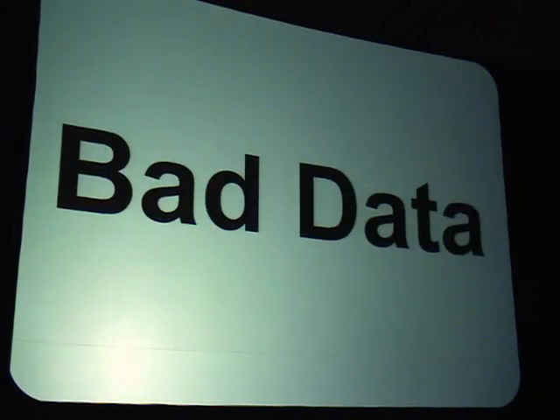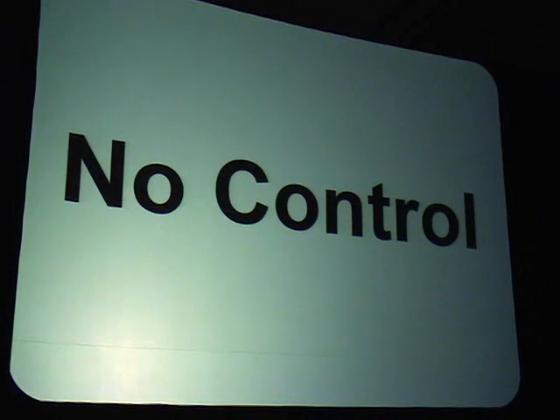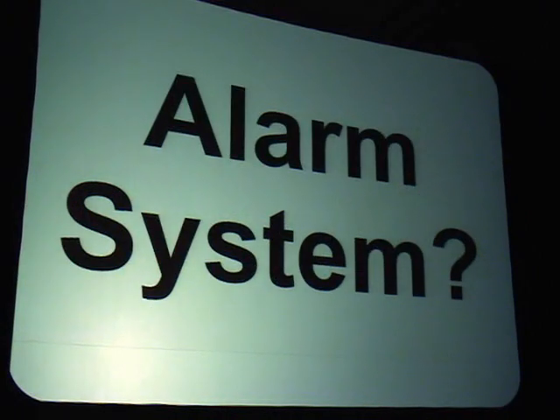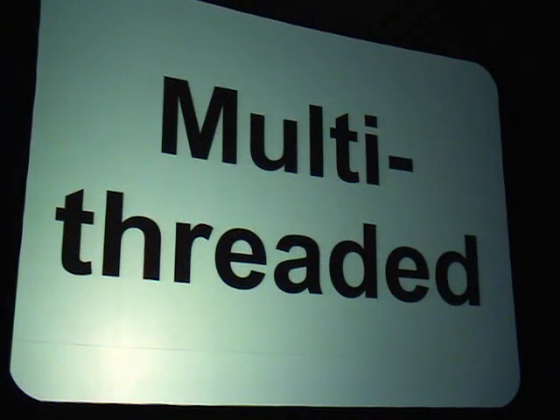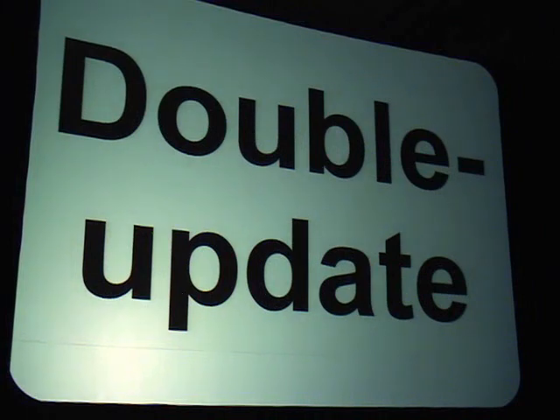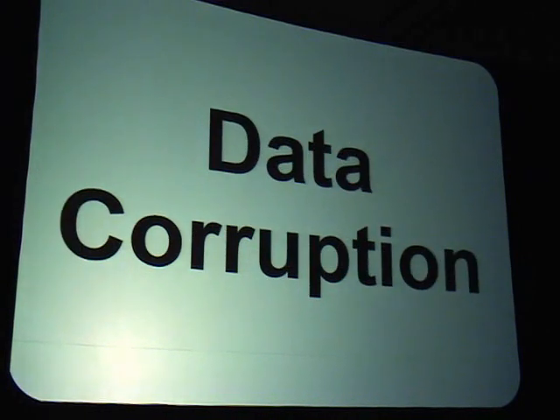But why did this occur? What was the root cause of it? Well, we know what the problem was with MISO. It didn't handle bad data very well. It wasn't very robust. But they didn't have control over the bad data either. But what happened with that alarm system? Well, the alarm system was a multi-threaded application, and it contained a race condition. Specifically, there was a double update problem. You could have 2 threads updating the same piece of data at the same time, and that would corrupt that piece of data. When the display system tried to read it, it would fall into an infinite loop, and it would stop updating.